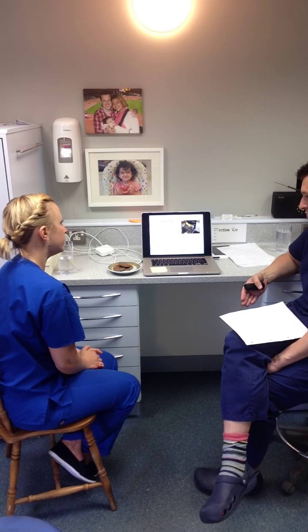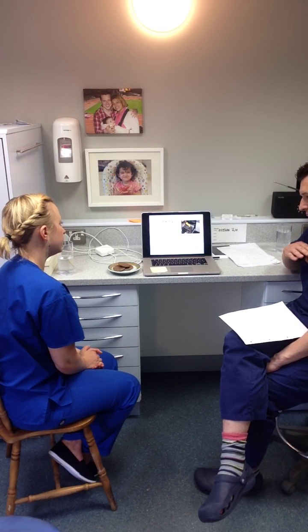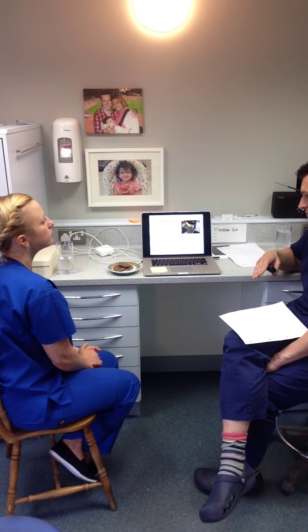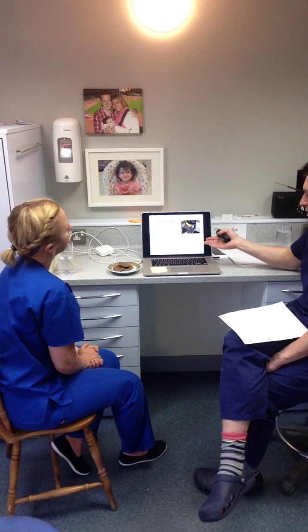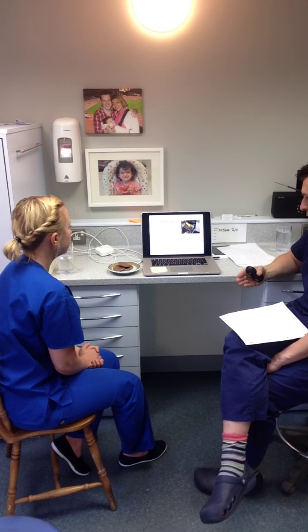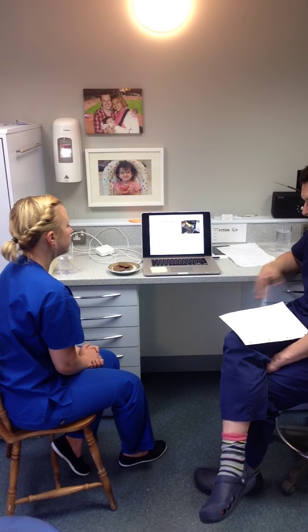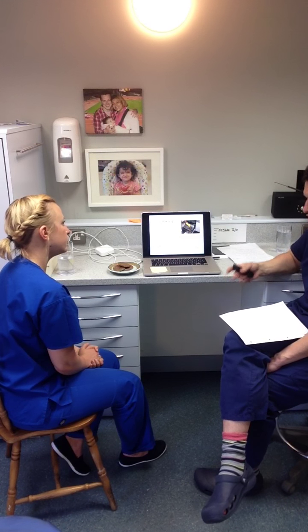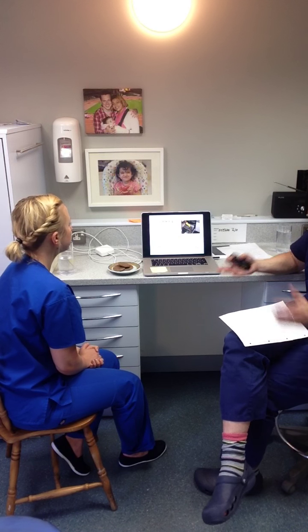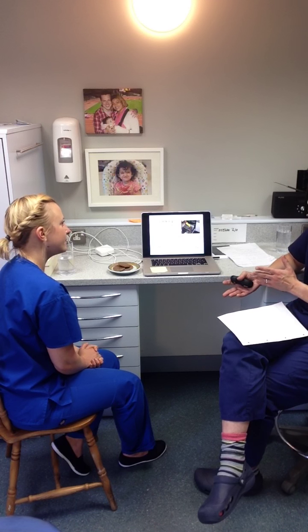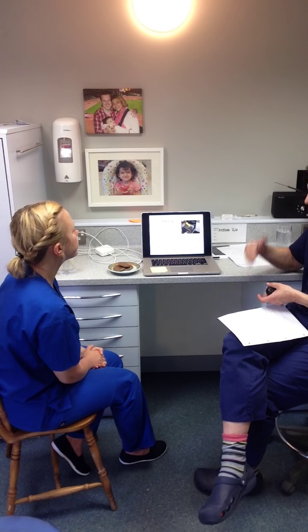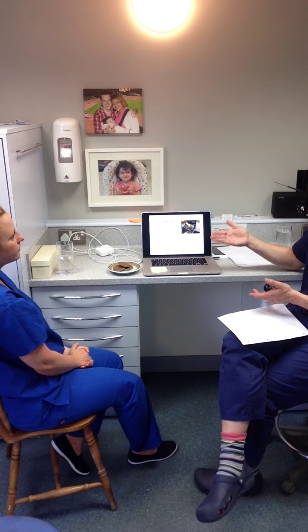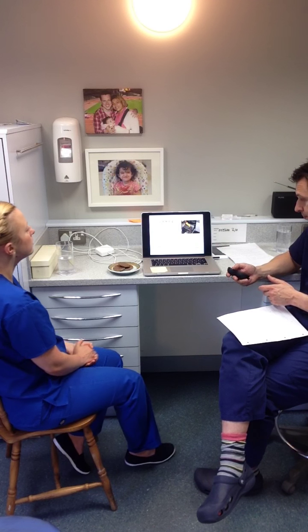And there's a thermal disinfection stage where the temperature is raised and held at a preset disinfection holding temperature. And for instance, that can be 80 degrees C for 10 minutes. And then there's a drying stage where it purges the load and chamber with heated air. It removes all that residual moisture, so it basically dries it completely. So at the end of the washer disinfector stage, you'd hope that it'd be disinfected, but it wouldn't be sterile. But then you'd be able to validate that the disinfection stage has been completed and the washing stage has been completed.